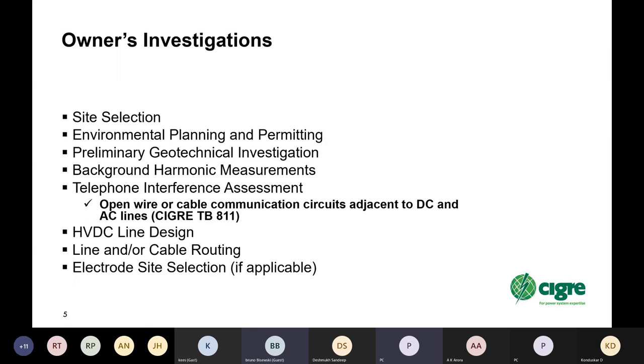And there's just been a very good new technical brochure released from CIGRE, technical brochure 811, which deals with telephone interference from HVDC lines in great detail and summarizes all the knowledge that practically is available there, thanks to CIGRE for providing that. And the HVDC line design, of course, needs to be done prior to the specification so that you have the parameters of the line to include in the specification so that the DC designers can design the HVDC system, a line and or cable routing for the HVDC system, and electrode site selection if you're going to put in electrodes.